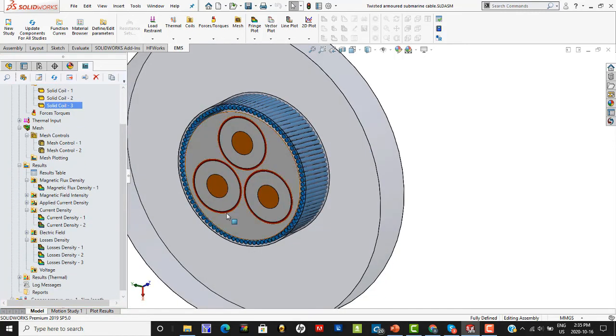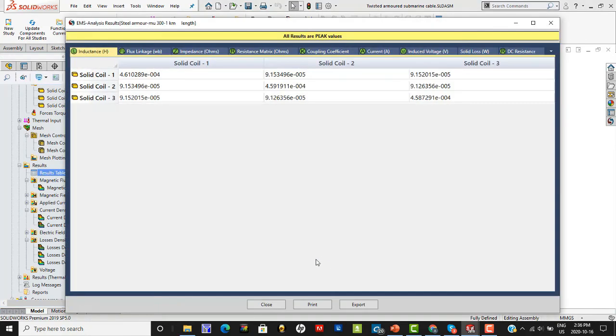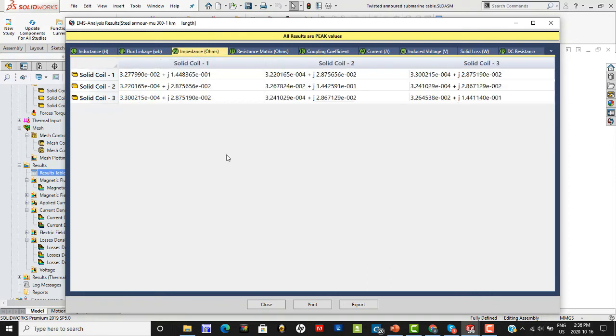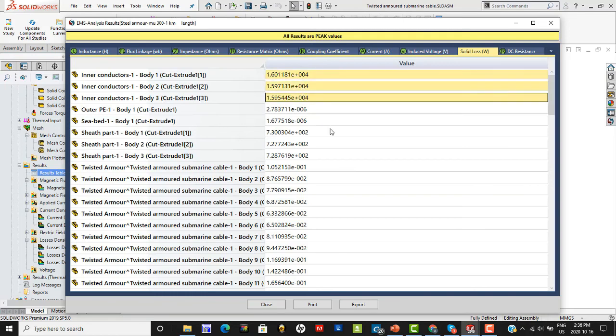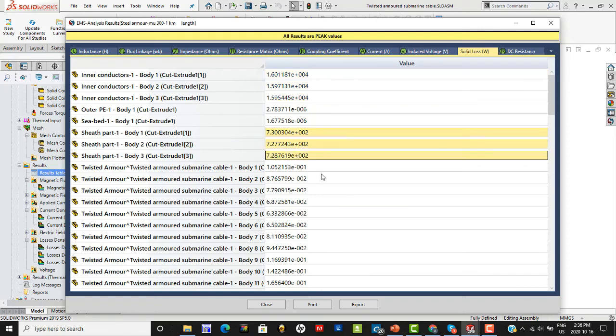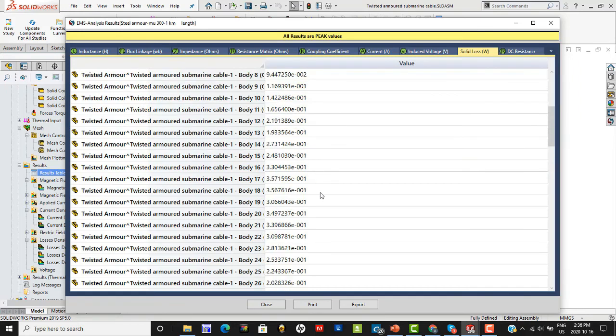Prior to this webinar, I ran the simulation so we can jump straight into the results. Many results are packaged into a result table. For example, you can calculate the inductance — both self and mutual inductance — for all the conductors. The impedance is also calculated. Finally, one can look at all the losses: the solid I²R copper losses occurring in the conductor, the losses in the lead sheath, and all losses occurring in the twisted armor are produced in this table.